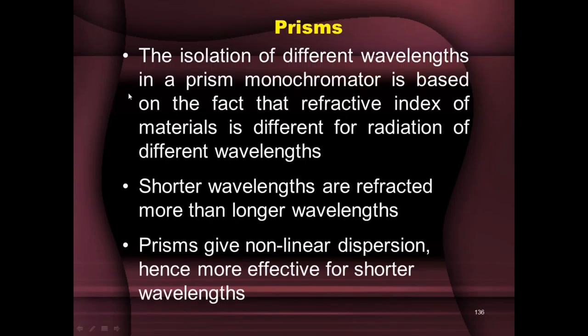We start off with prisms. The isolation of different wavelengths in a prism monochromator is based on the fact that the refractive index of materials is different for radiation of different wavelengths. So if you say the refractive index of a material is a certain value, that's measured at a particular wavelength. If you change the wavelength, then the refractive index will also be different. It all depends on the angle of refraction.